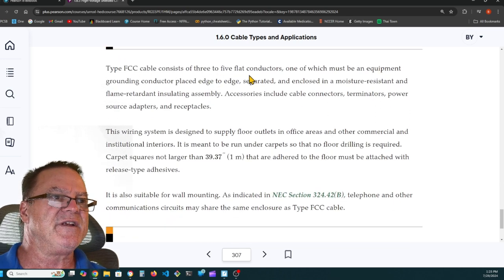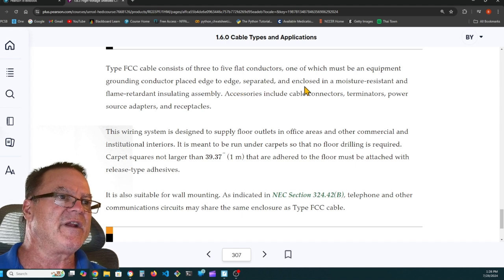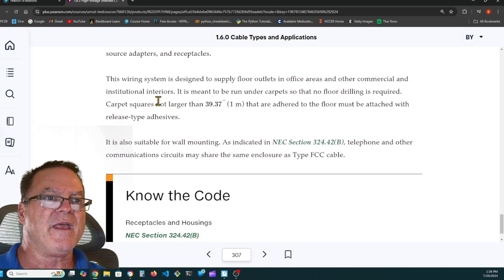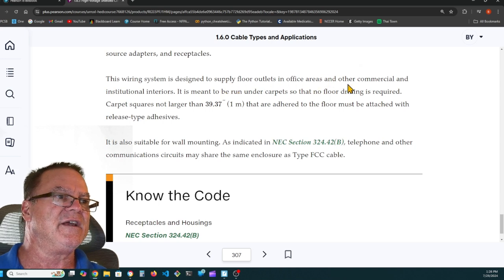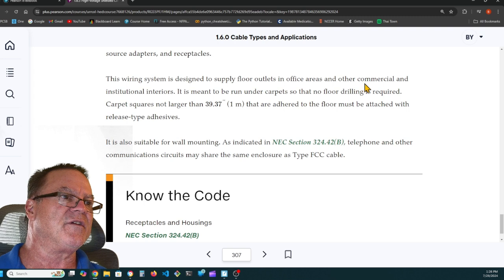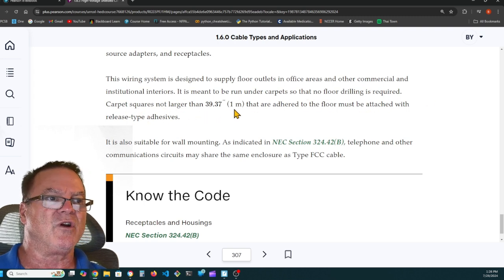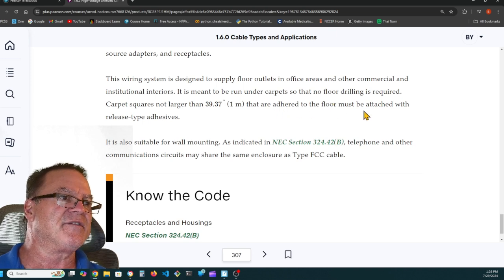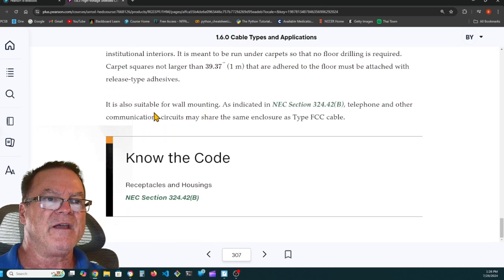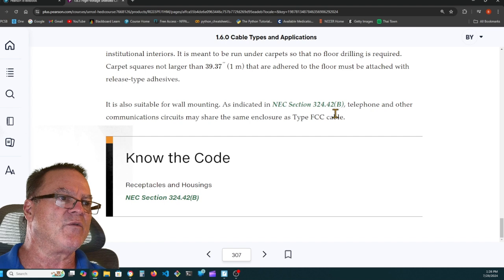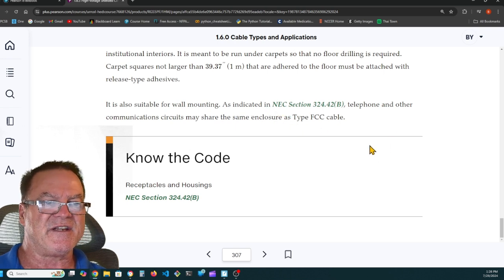Type FCC cable consists of 3 to 5 flat conductors, one of which must be an equipment grounding conductor, placed edge to edge, separated and enclosed in a moisture-resistant and flame-retardant insulating assembly. Accessories include cable connectors, terminators, power source adapters, and receptacles. This wiring system is designed to supply floor outlets in office areas and other commercial and institutional interiors. It's meant to be run under carpets so that no flooring drilling is required. Carpet squares no larger than 1 meter square that are adhered to the floor must be attached with release type adhesive. It's also suitable for wall mounting as indicated in 324.42(B). Telephone and other telecommunications circuits may share the same enclosure as type FCC cable.